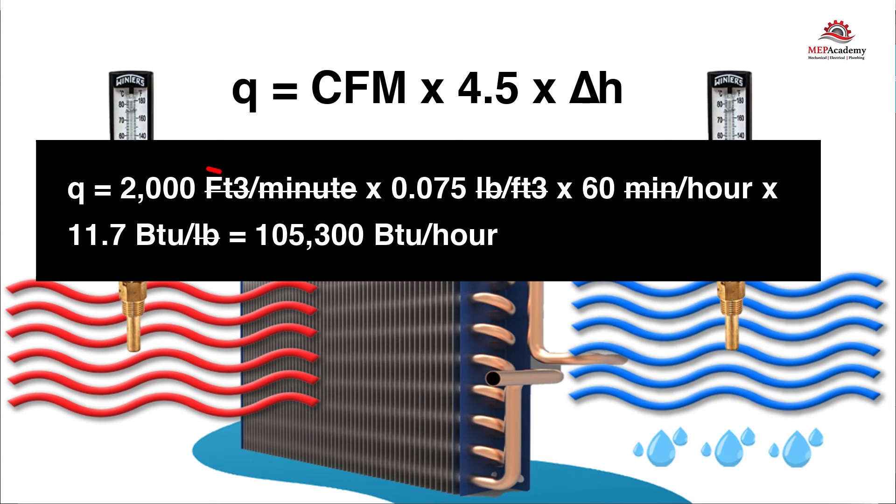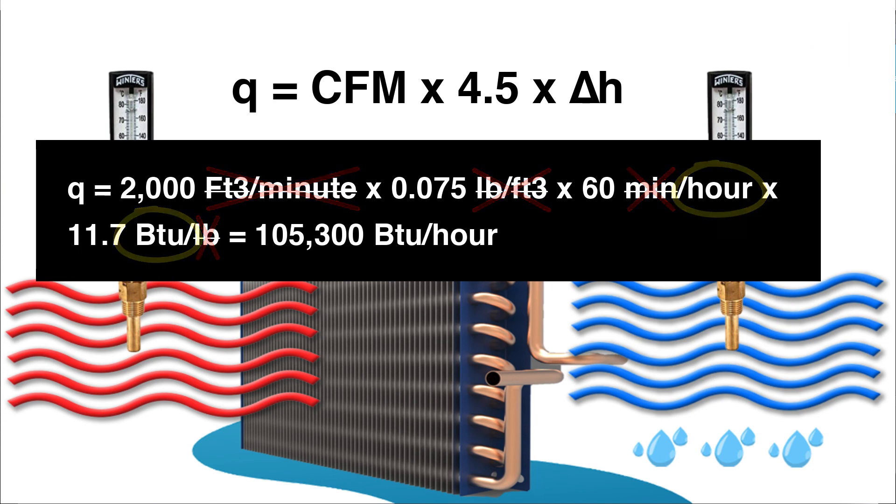Q equals 2,000 cubic feet per minute times 0.075 pounds per cubic foot times 60 minutes per hour times 11.7 BTUs per pound equals 105,300 BTUs per hour. If you liked that video, please give it a thumbs up and subscribe to our channel. Thank you.